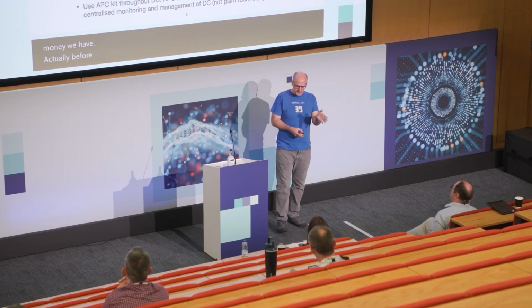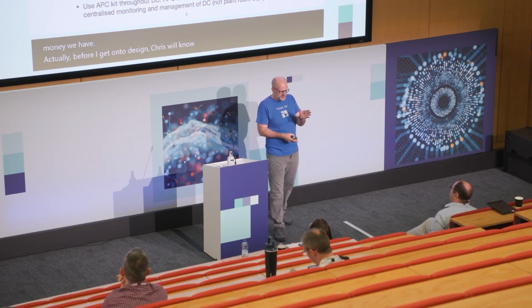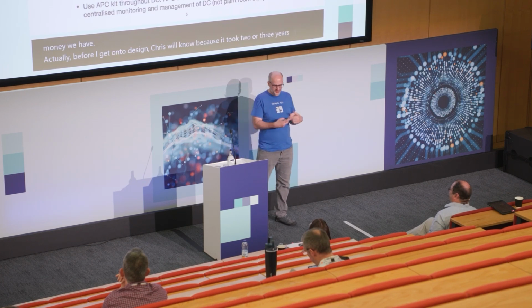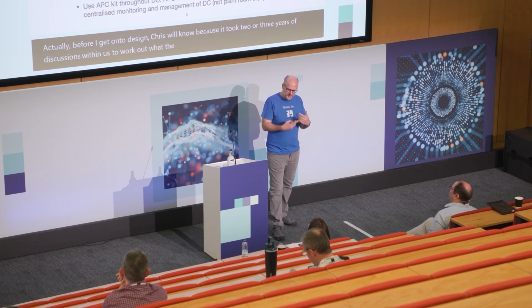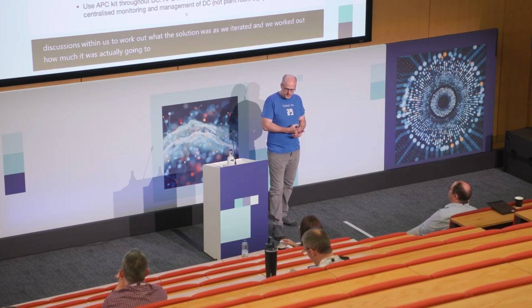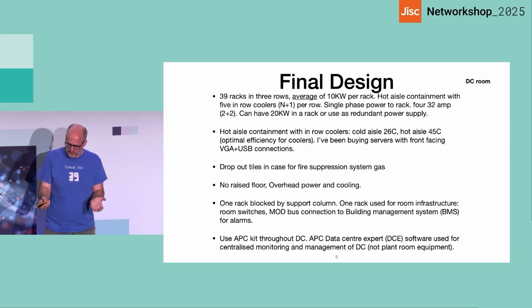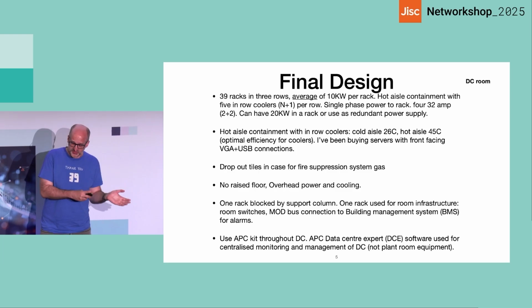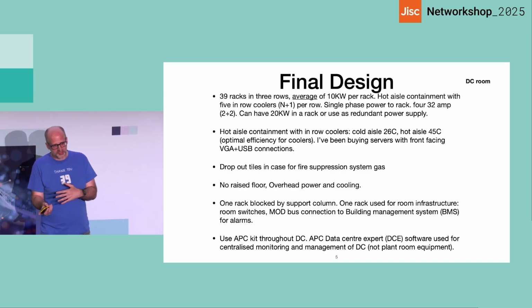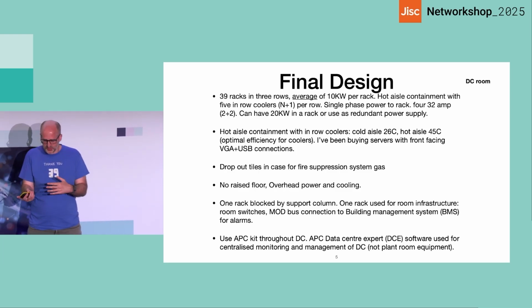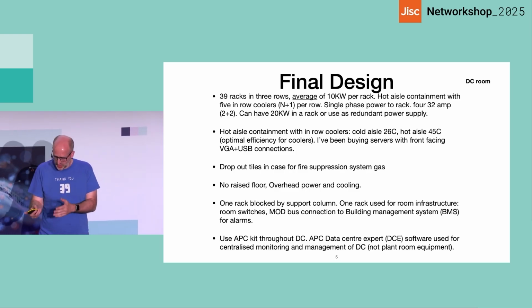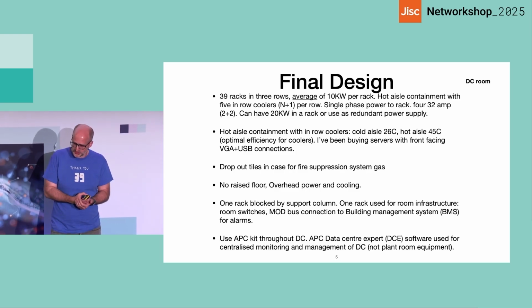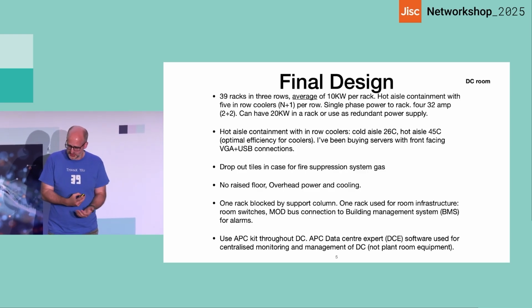Before I get on to the design, Chris will know, because it took 2 or 3 years of discussions within us to work out what the solution was as we iterated and worked out how much it was actually going to cost. Eventually, we came forward with this design. We're going to have a room reusing the old data center. It's going to contain 39 racks at an average of 10 kilowatts a rack. That's quite low by modern standards, but we can be a bit flexible, so we can go up to 20 kilowatts with the 4 single-phase PDUs we have in each rack, or we can go redundant 10 kilowatts because we've got A and B power supplies.